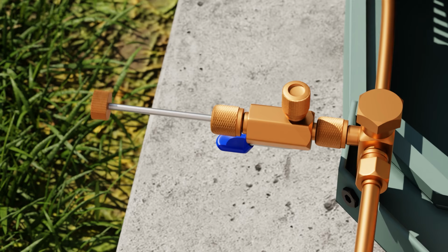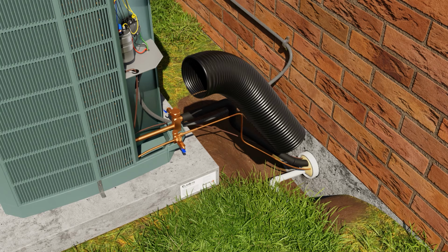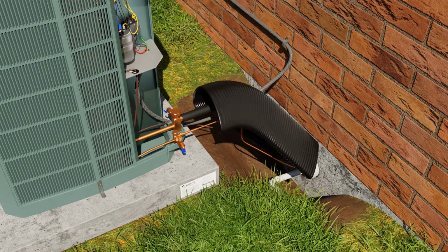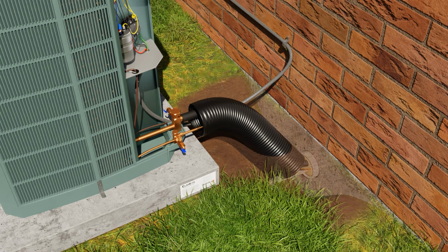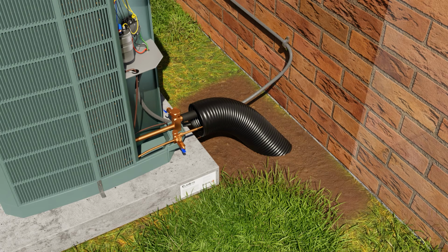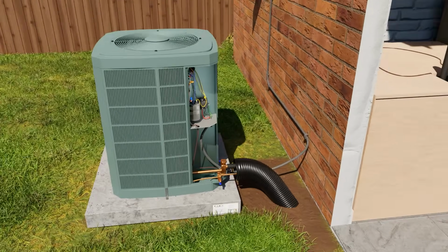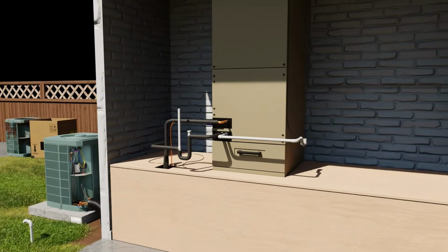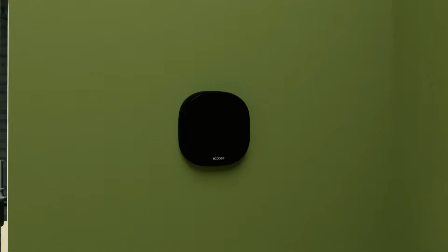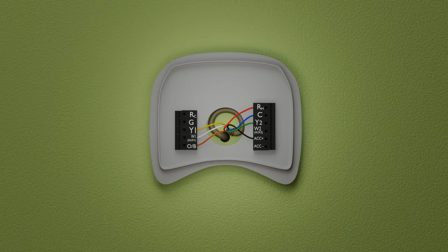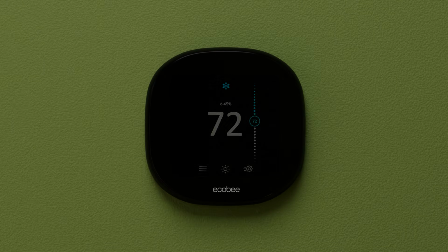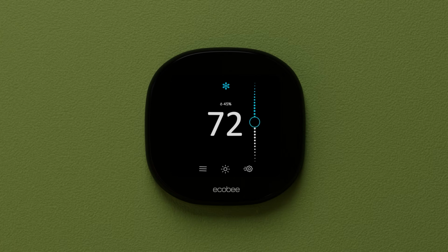Follow this process exactly. This could actually be done later, but we showed at this point that we're going to add the corrugated tubing that protects the copper from lawn equipment. That's the only reason it's there. It doesn't create any sort of a watertight seal. Make sure your thermostat is installed and wired properly. Ensure that it's level and that you don't leave any fingerprints on the thermostat or on the wall.